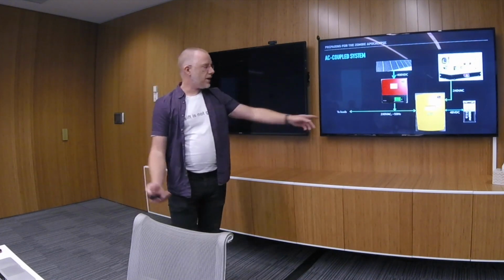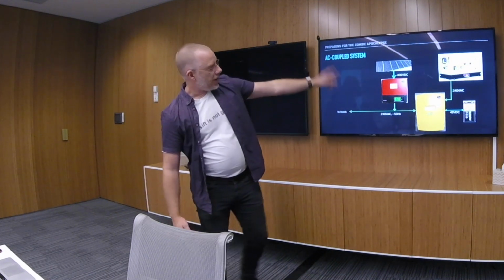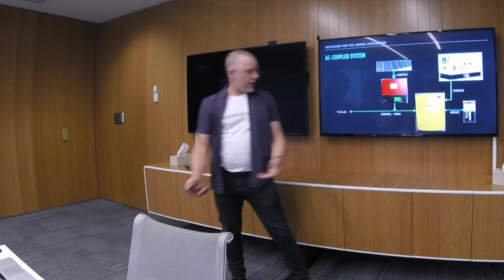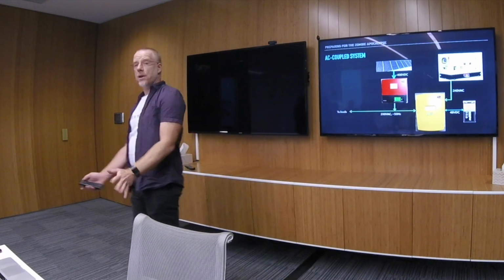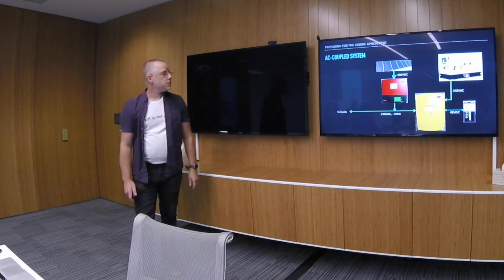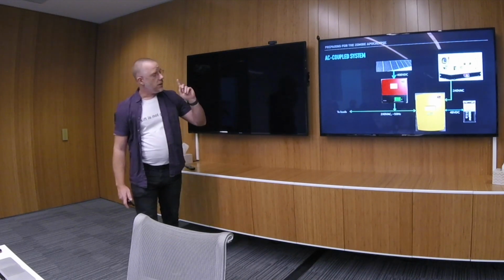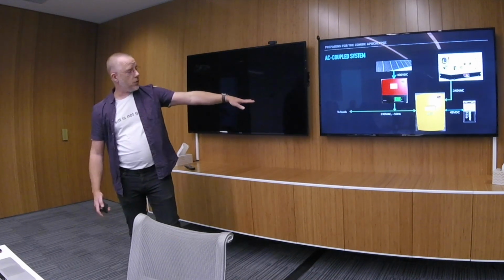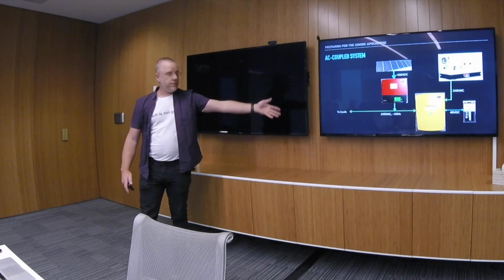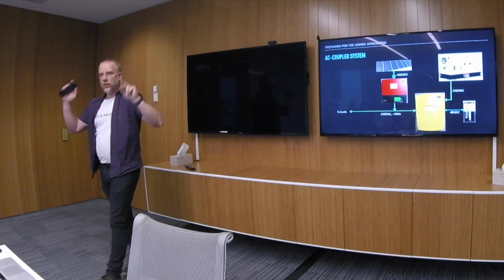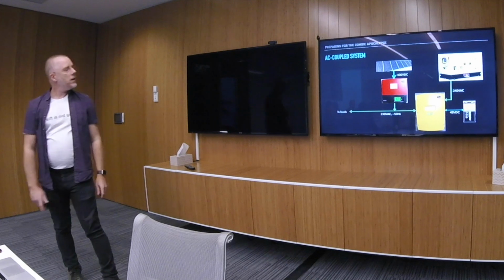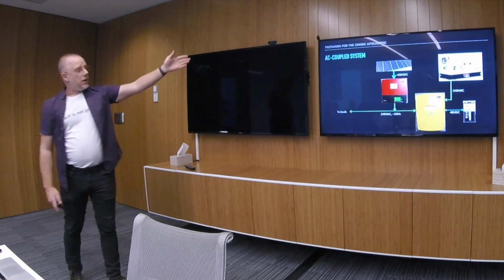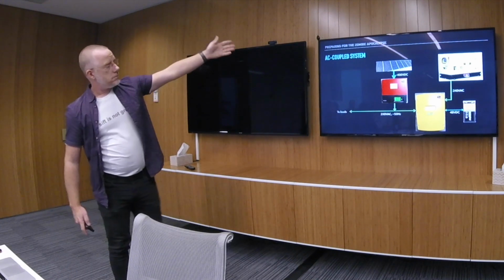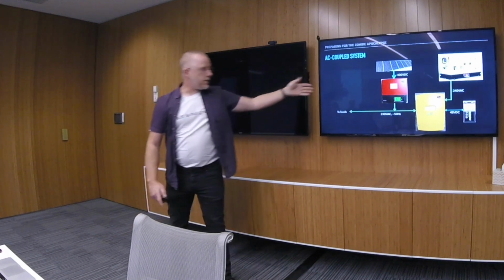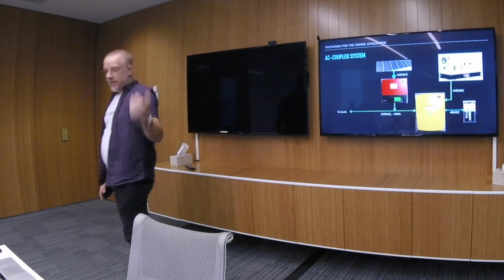So the way the system's architected: the battery inverter manages the battery. It's the only thing that's connected to the battery, nothing else is. The battery inverter produces the 240 volt grid at air quotes 50 hertz, and I'll explain the air quotes in a minute. But then your solar inverter, the panels connect to the solar inverter, then you attach to that grid.